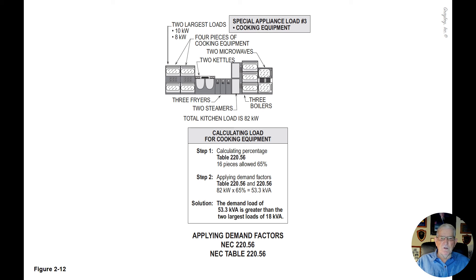Step 2: Table 220.56 allows 65% of the 82 kW, which equals 53.3 kVA. That is the solution — that is the answer.